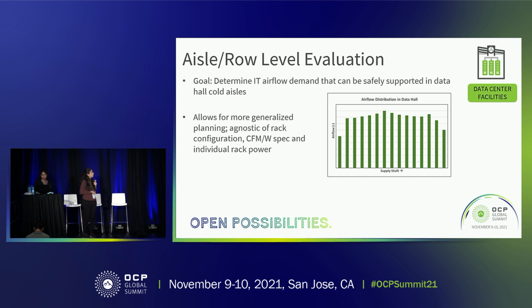So let's take a closer look at the aisle or the row level evaluation. The goal here was really to determine the cooling capacity, or the IT airflow demand, that can be supported by each and every aisle in the data hall. And the reason we chose the IT airflow and not the IT power or a certain rack configuration is because when we talk about the IT airflow or the cooling capacity, it becomes agnostic of the rack type and the different rack metrics, etc. So it can be applied for all kinds of hardware directly. If you look at the graph that I've presented, it clearly shows that among the different supply shafts and the different cold aisles that one can have in the data hall, there can be a varied distribution. And as I mentioned before, we then become limited by the lowest airflow available in the cold aisle if we are going for uniform deployment.